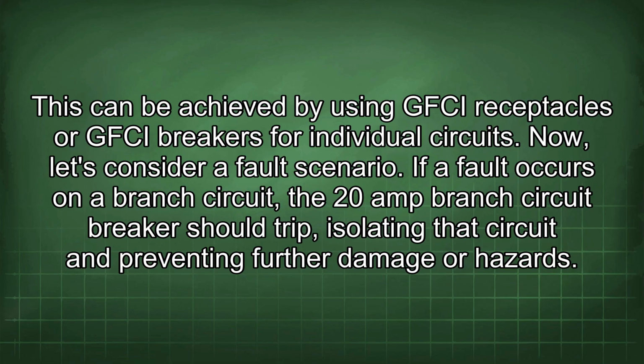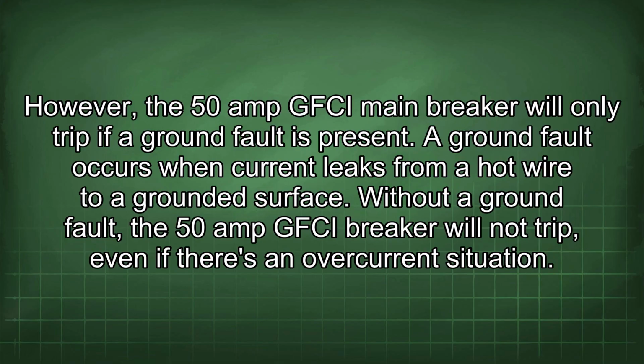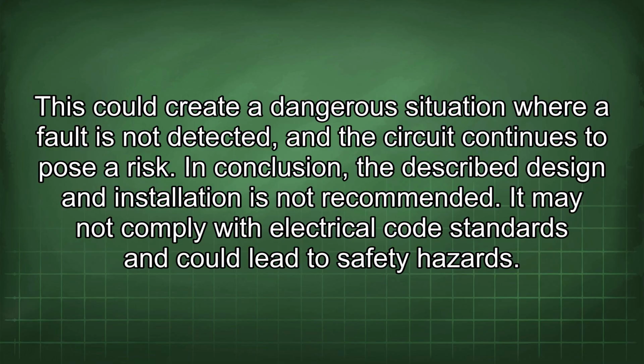Now, let's consider a fault scenario. If a fault occurs on a branch circuit, the 20-amp branch circuit breaker should trip, isolating that circuit and preventing further damage or hazards. However, the 50-amp GFCI main breaker will only trip if a ground fault is present. A ground fault occurs when current leaks from a hot wire to a grounded surface. Without a ground fault, the 50-amp GFCI breaker will not trip, even if there's an overcurrent situation. This could create a dangerous situation where a fault is not detected and the circuit continues to pose a risk.